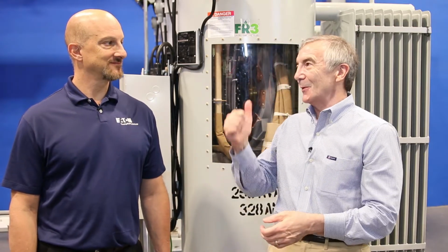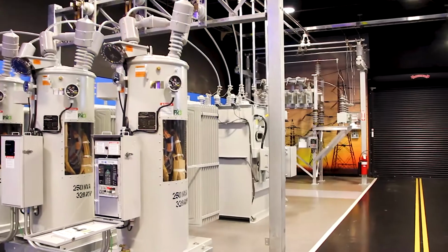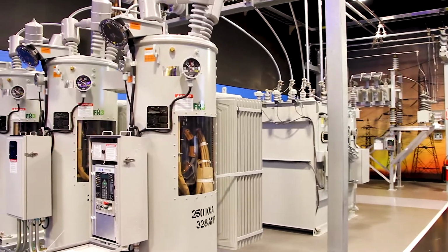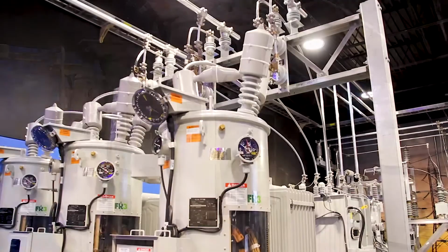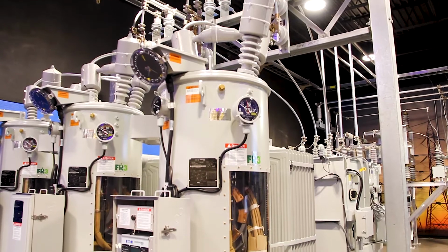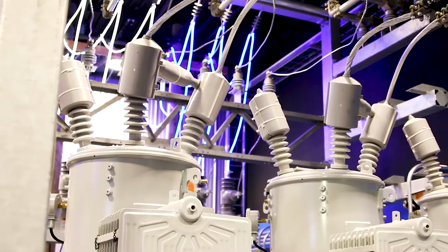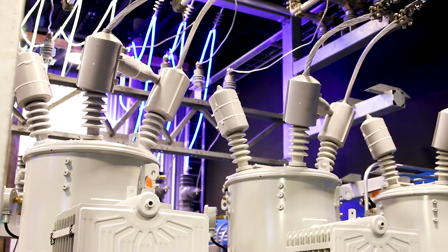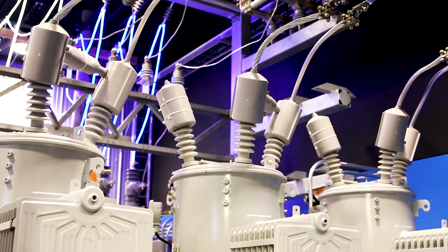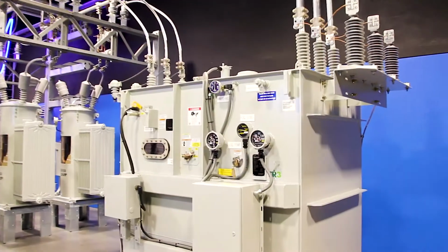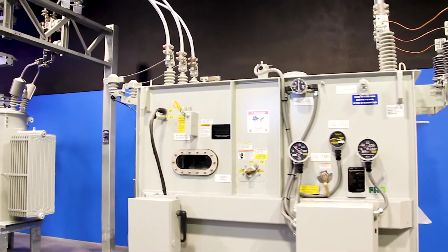But Dan, exactly what's the problem when you get a whole lot of power coming back the wrong way? That's a good question, Lee. So what happens is the utility wants to send power from a high voltage level down to the load, and it drops along the way. What happens when you install large bulk sections of solar, whether it's many homes or a large commercial or industrial application, is they actually end up putting power into the substation. So back here at our transformer, our voltage actually goes up, and then it goes back down to the load.